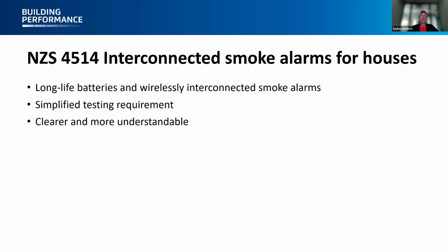The testing requirement is simplified. There was something there that the owner had to do a smoke test with their alarms, and that was removed. And the document's language and explanations are aimed towards the homeowner, not necessarily fire engineers, so that's been made more explicit.